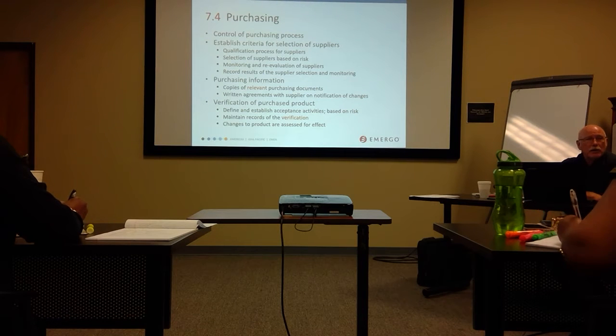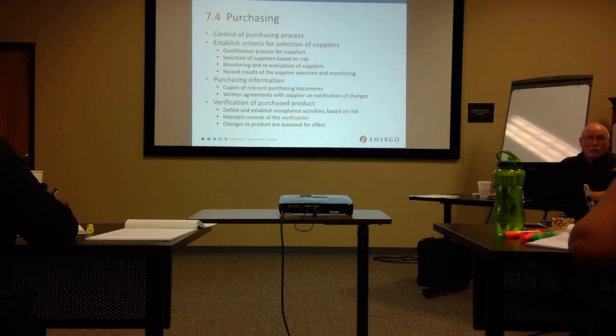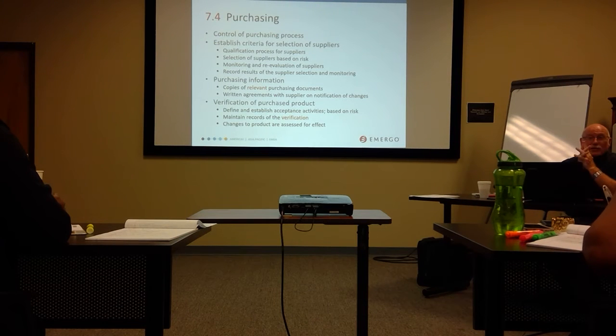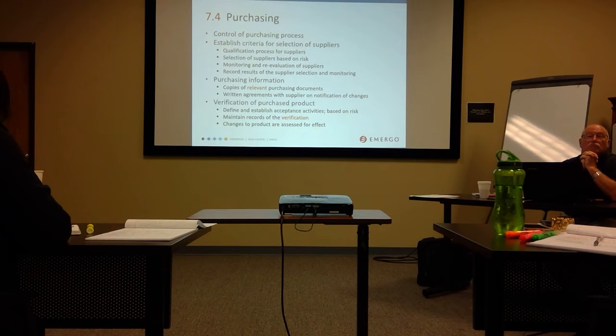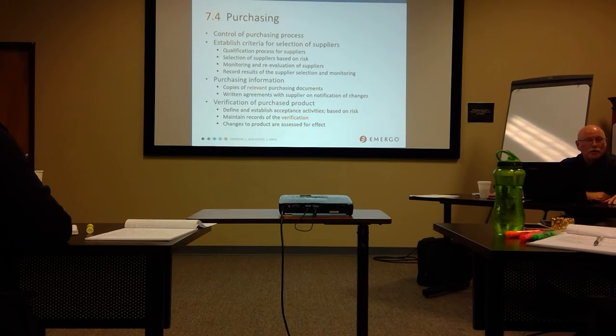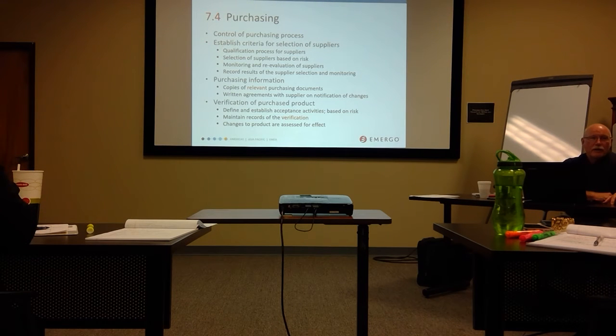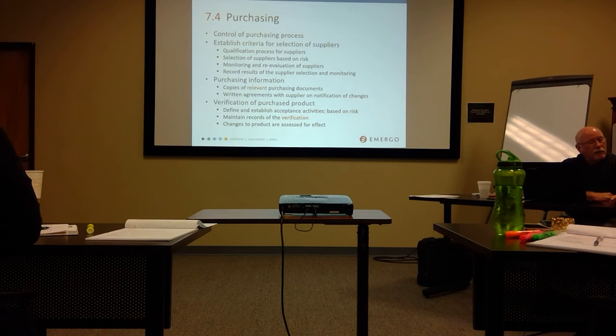This also applies to service providers. How about your notified body? Those guys are fairly important — they determine whether or not you're on the market in the EU, Canada, Australia, and lots of other places. Where you position these is up to you. There is no one right way, with the exception that all contract manufacturers should be considered critical. Other than that, it's your call based on your quality risk assessment. Service providers should be in there too. We see initial qualification — what do we require? We require that you provide us what we need as defined by the purchase order, drawings, whatever it may be. For some, we may require ISO certification. We may require an on-site qualification visit. We also track and trend non-conforming products that you send to us — that is right out of the regulation.